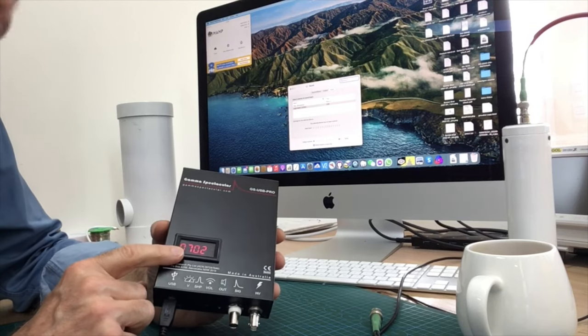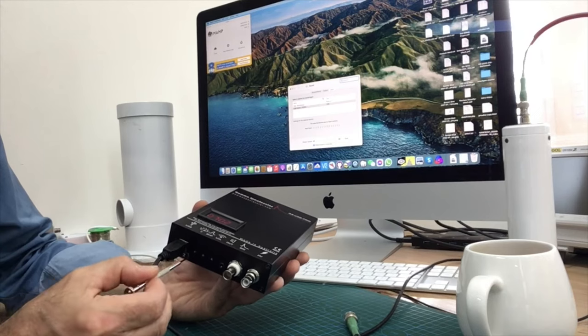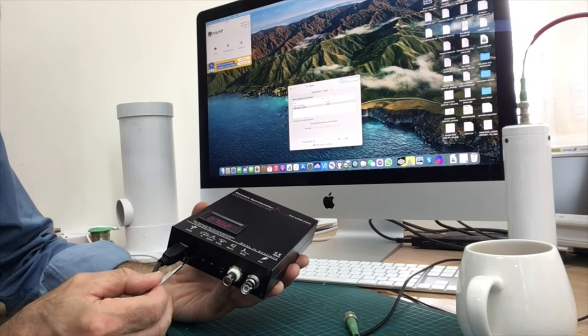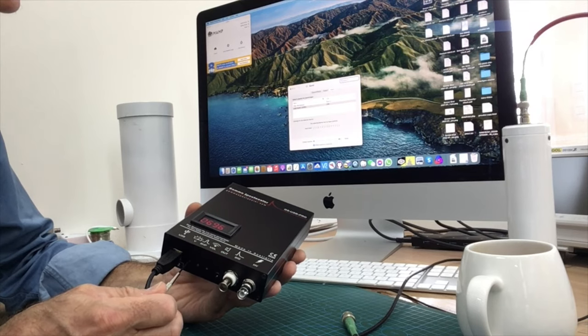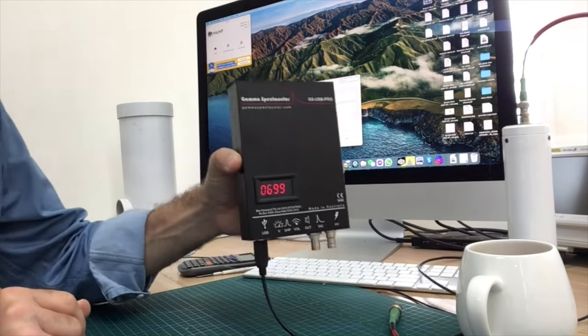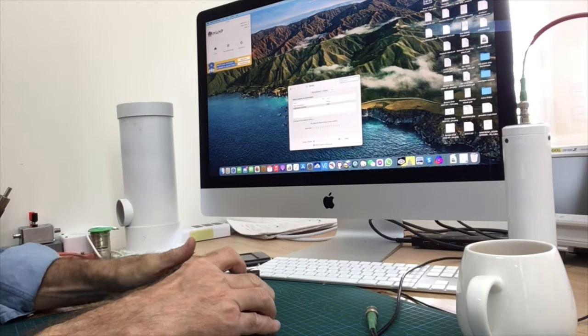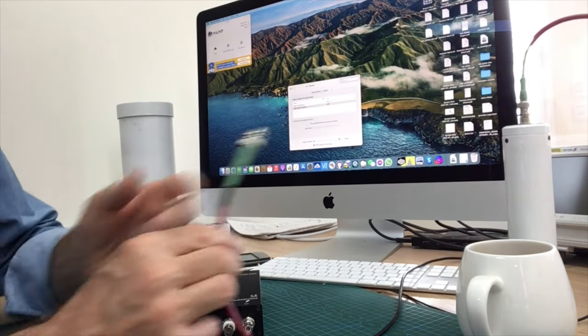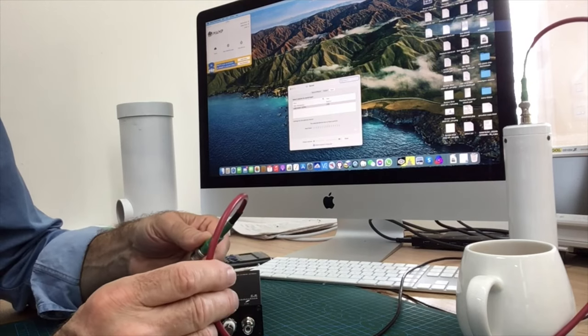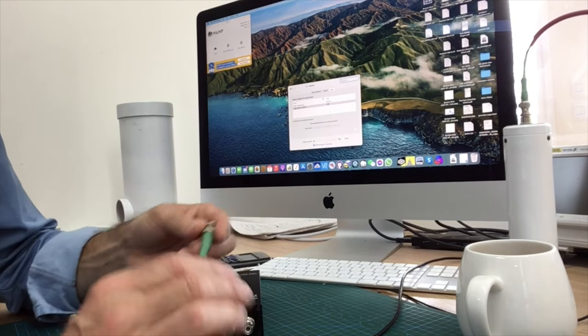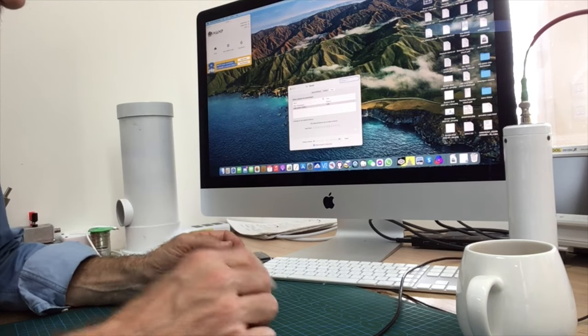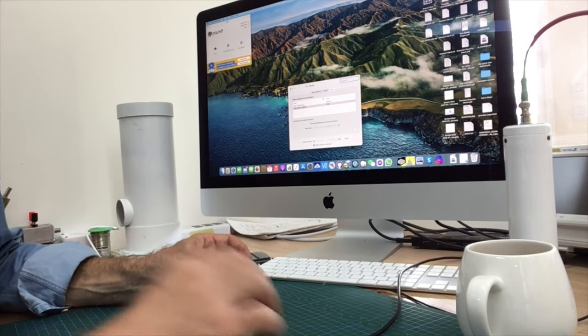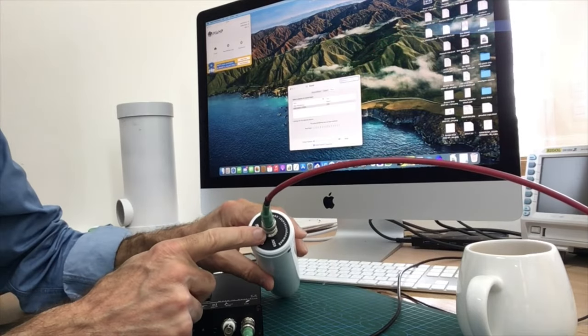The voltage comes on automatically. If you need to adjust the voltage, this is done here with the trimmer potentiometer on the end. We can set the voltage to 700 volts, 699, that's near enough. And then it's just a matter of connecting our detector. Here we use a quality RG58C which is a 50 ohm coaxial cable capable of handling high voltage, and that connects to the SHV connector and to the detector.